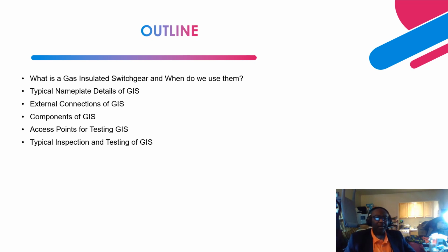Now let's talk about the outline. The first item is what a gas insulated switchgear is and when we use it. Then typical nameplate details of GIS. We'll walk through all the nameplate parameters required for the GIS, and usually the nameplate details are stamped and stenciled on a plate after the factory acceptance testing, and become part and parcel of the GIS throughout its operating life cycle.